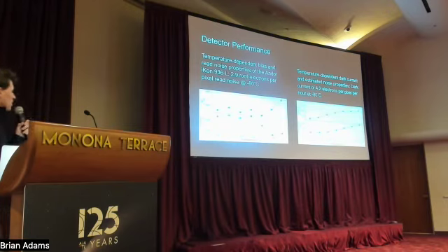This is the quantum efficiency of the camera. It's this green line here. It's really good, above 90% in that visible range, which is where we want to be. Now, this is a nice flat field image in the background where you can see the structure of our sensor, and hopefully after calibration that goes away. But what this sensor can do, it has 2.9 root electrons per pixel read noise at -80 Celsius. So it's a very quiet read noise camera.